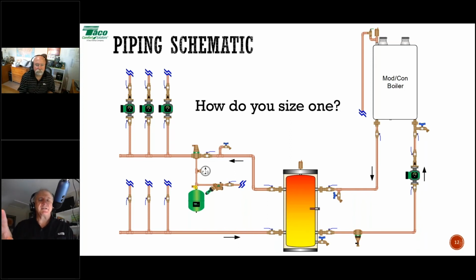You can short cycle a ModCon boiler, to the extent that they can be short cycled, which is pretty remarkable. Not only does the boiler never fire long enough to get efficient, but you're also killing components. You're going to short cycle moving parts into an early grave. So there's no upside there. Yeah, go ahead, Rick. Well, another point is nowadays these boilers are keeping track too. What do I mean by that? They know how many times you've cycled that. It keeps track of every time you fired it.